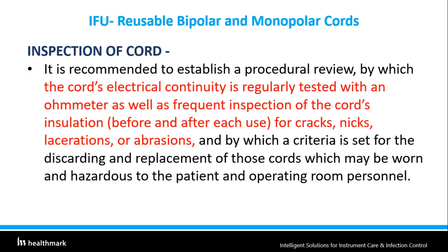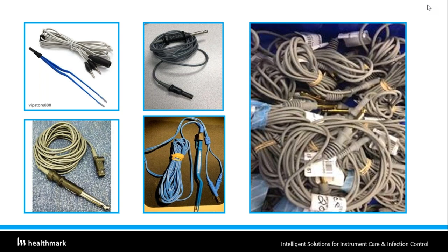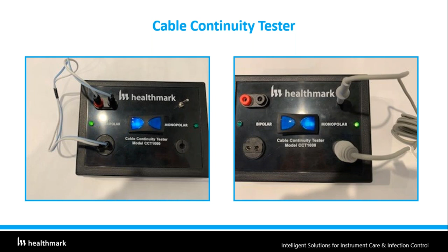you can see that there are buckets of them in the SPD department, and some departments do have a really good system to check them. For example, in this area that you see, they noted 20 uses on those, so those are put in a basket or bucket to be disposed of. But it's difficult to really keep track of them. So some of the users at the hospital came to us and asked if we could have something to check them. On the next slide, you can see that we came up with this continuity tester, which is pretty easy to use. If there is a green light, it's okay. If there is no green light, you need to probably pitch that item or take a look at it. With that, next slide, please.